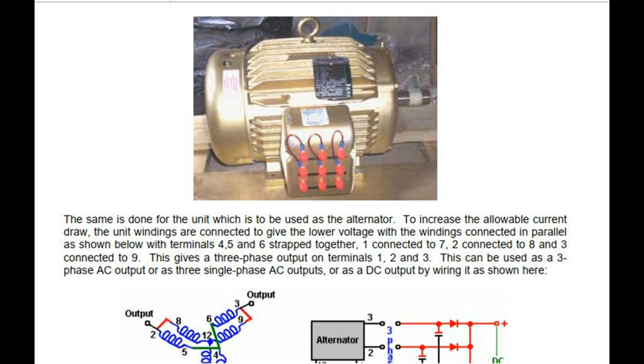The same is done for the unit which is to be used as the alternator. To increase the allowable current draw, the unit windings are connected to give the lower voltage with the windings connected in parallel as shown below, with terminals 4, 5 and 6 strapped together, 1 connected to 7, 2 connected to 8 and 3 connected to 9. This gives a 3-phase output on terminals 1, 2 and 3. This can be used as a 3-phase AC output or as 3 single-phase AC outputs, or as a DC output by wiring it as shown here.